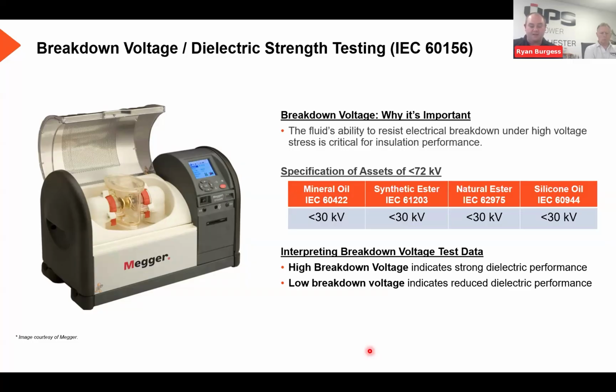So what causes that drop? As I said, the main drop in that performance is due to the moisture and other contaminants. So the basic remedy usually first time is to take a resample. As Dan was saying, that's usually down to a poor sample, whether you've not cleaned the sample point correctly, you've taken the sample in the wet, or you've just used dirty equipment. And then in terms of looking at what the results show you, high breakdown voltage indicates good dielectric strength, which indicates good insulating properties, whereas a reduced or a low breakdown is a reduced performance in dielectric strength and in insulating properties.